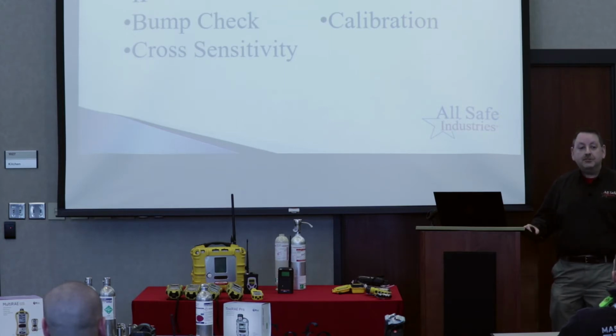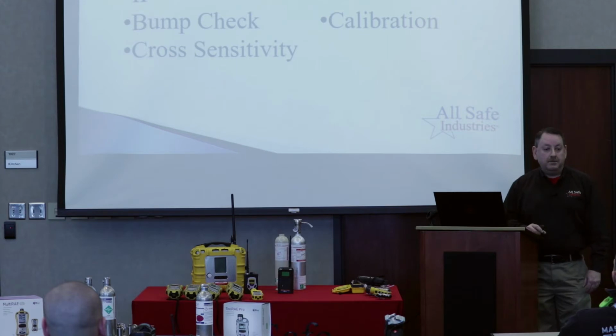And then when we're measuring volatile organic compounds, one of the things we need to know about each specific compound is what is the IP, or the ionization potential. It's a very specific number, and as long as your PID is larger than the number of the compound, we'll be able to detect that with the PID sensor that's in your meter. Okay, so we'll talk quite a bit about ionization potential. And correction factors is what CFs are.